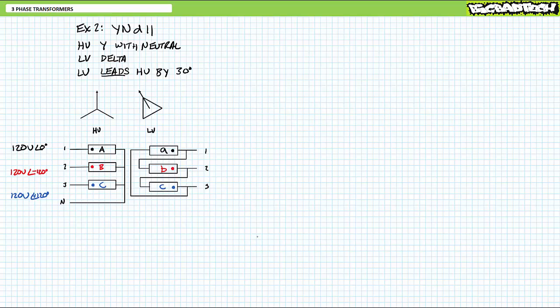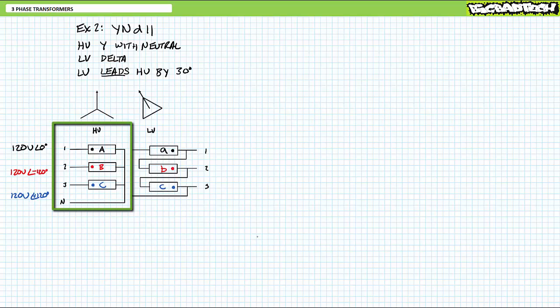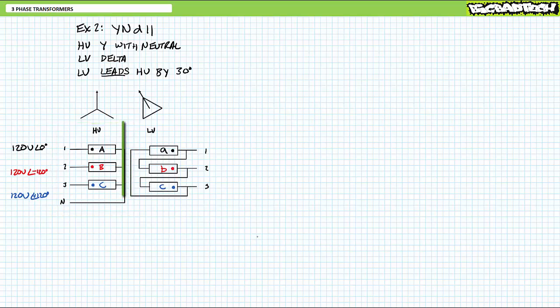Let's take a look at the simplified connection diagram for a YND11 configured three-phase transformer. The Y-configured high voltage side again looks exactly like you'd expect, where the non-dotted ends of three high voltage windings are tied together to form the central neutral connected node of a Y — identical to the high voltage input of our previous YND1 example. For the delta-configured low voltage side, it still ties the dissimilar ends together — dots to no-dots in a continuous ring — only this time it does so in reverse order. This is what induces the eleven o'clock or thirty degrees leading shift, as opposed to the one o'clock or thirty-degree lagging shift of the previous YND1 example.